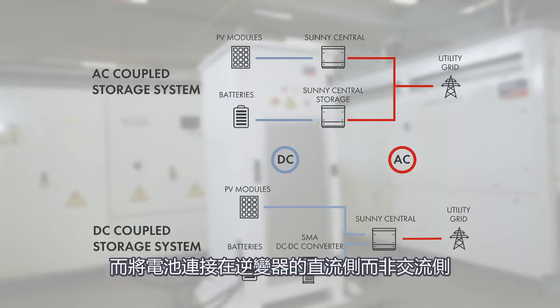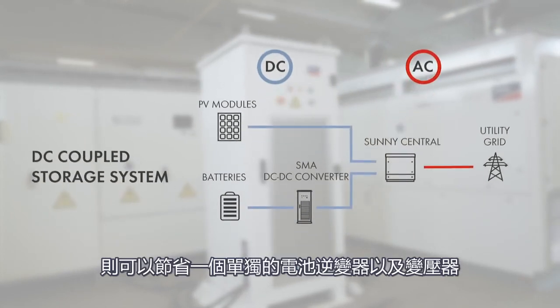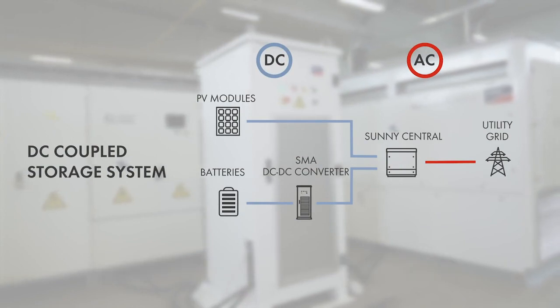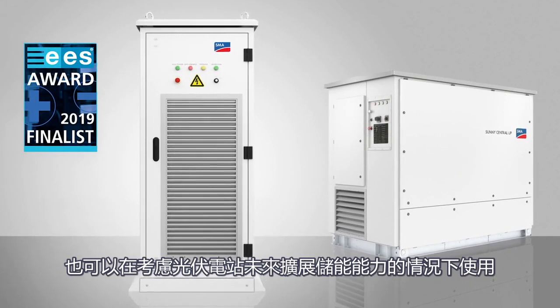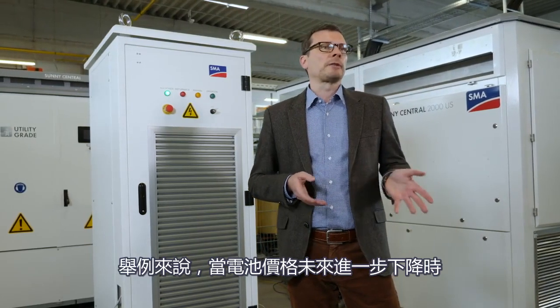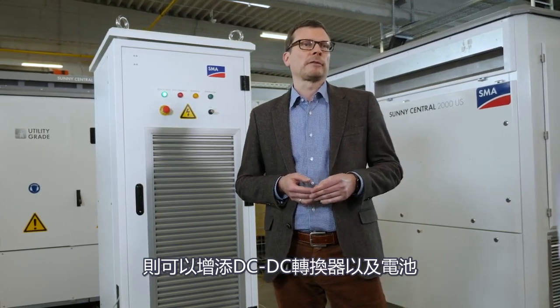Connecting the battery on the DC side of the inverter instead of the AC side saves a separate battery inverter and a transformer as well. That means less investment in equipment, so lower capex, and less losses in the system. The DC-DC converter as well as the battery can be added later on, for example, when battery prices have come down further.